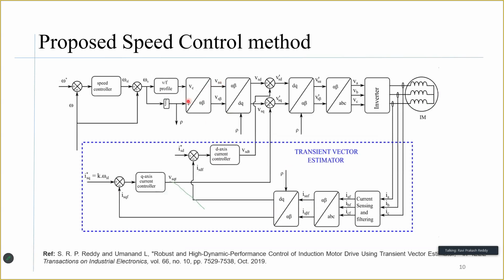In the proposed speed control method, we have V by F control or the scalar control in the steady state portion. We have a speed reference being compared with speed feedback. The speed controller is going to give you slip, and we also have a feedback compensation of the omega feedback. When both are added, we have the synchronous speed. The V by F profile of it is going to give you the control voltage. Once you have the control voltage and phase of it, you could actually transform them to alpha, beta, or ABC, and then compare with the appropriate triangle carriers. And once those PWM signals are given to the induction machine, the machine would spin at your set reference speed.